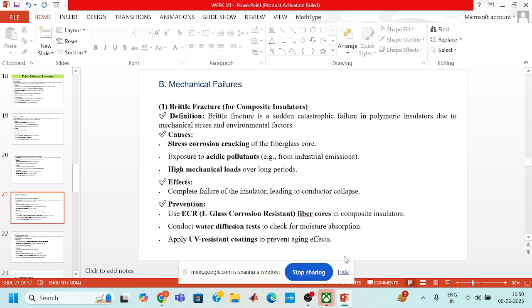So we can use ECR, which is E-glass corrosion resistant fiber, in composite insulators, and we can also conduct the water diffusion test to check the moisture absorption. Also, we apply UV resistant coatings to prevent the aging effects.